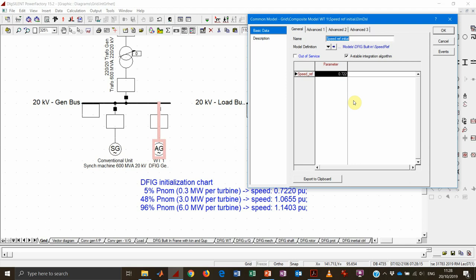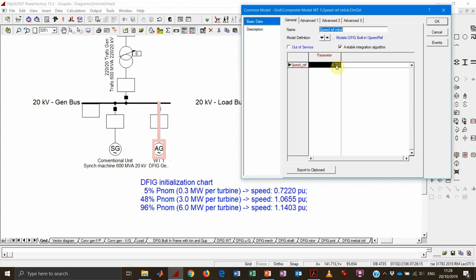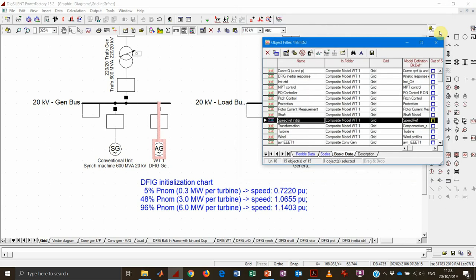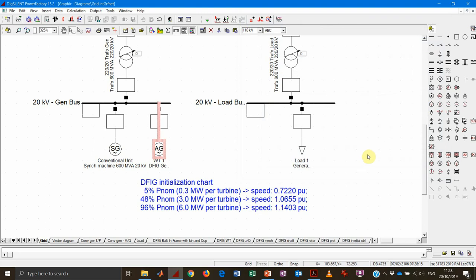The 'speed ref initial' block simply contains a constant value that we need to fill in. This value must be chosen according to the initial power — if we don't choose it properly the model will not initialize correctly. PowerFactory will not give an error; instead there will be a dynamic transient at the very beginning, and the larger the deviation between the set speed and the correct value, the larger the deviation in initial states — which could potentially lead to instability. According to these two values, the wind speed will be derived backward from the model.